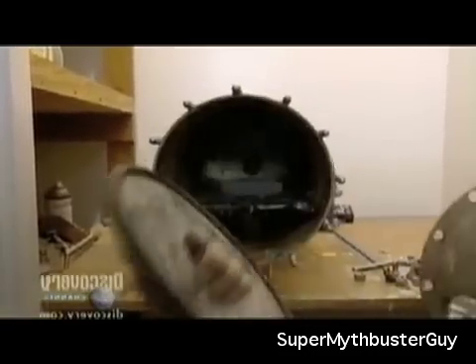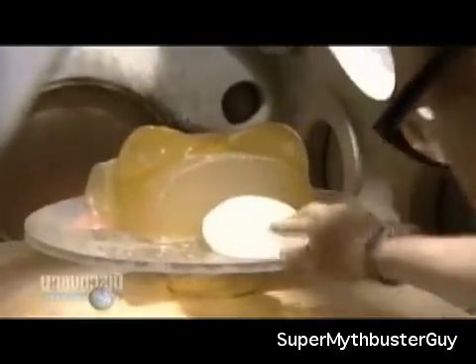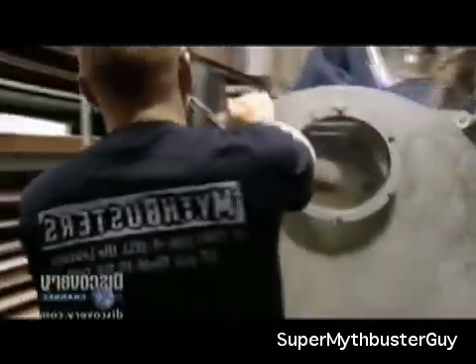No changes to the implant at high pressure, so it's back to the large chamber for another low-pressure altitude test. Within a few minutes, it's taken the equivalent of a rapid trip from the ocean's floor to the summit of Everest. Shall we go up to 30,000 feet?